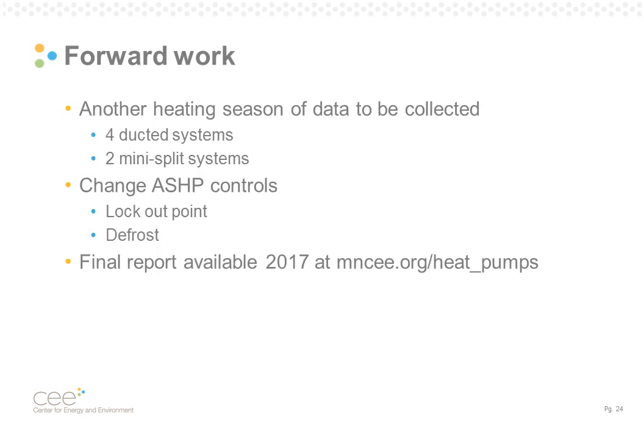So we have more work to do on this project. We have this upcoming heating season where we are going to be collecting data from all 6 sites. That's 4 ducted systems and 2 mini split systems we will be collecting data from. We are also going to be looking at changing some of the air source heat pump controls. So we are thinking of changing the lockout point on some of these units to below 10 degrees to see how the system performs below that set point.